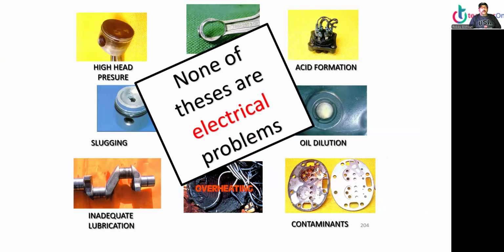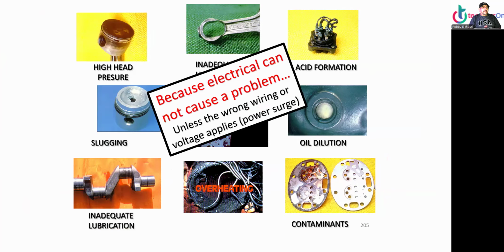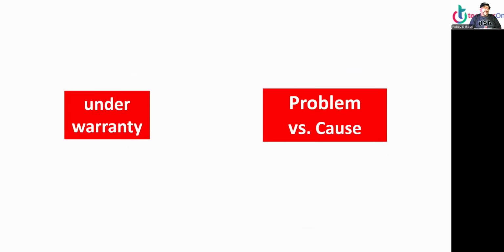None of these are electrical problems, because electrical is not a cause, only if it's wired wrong or we have a power surge. A relay, capacitor, overload will never cause a compressor to burn. We have protections. Now, let's talk about under warranty and let's talk about problem and cause.